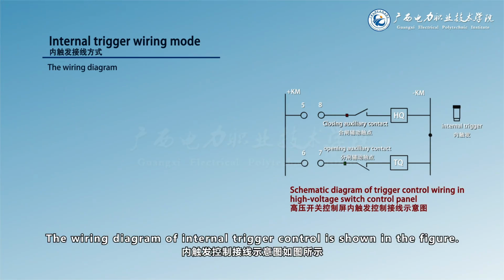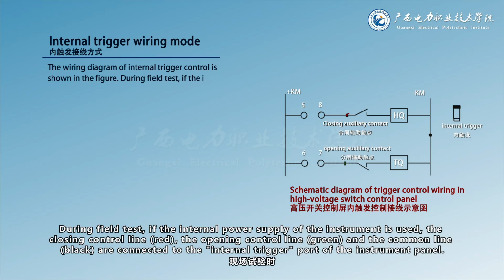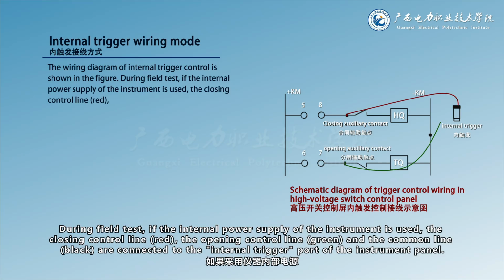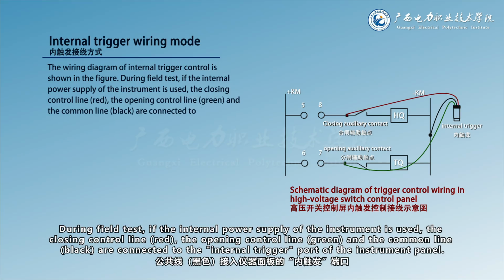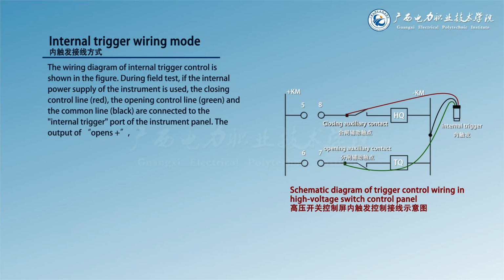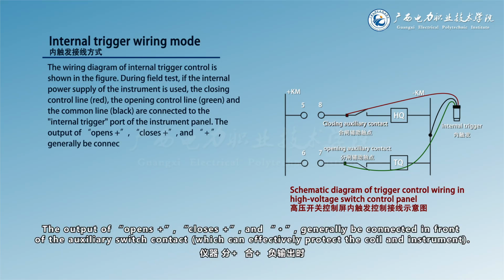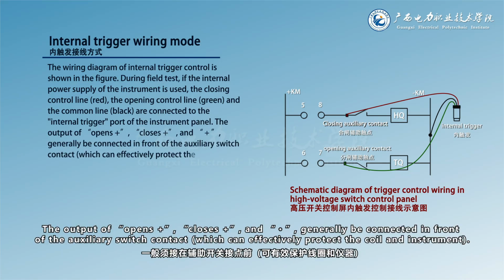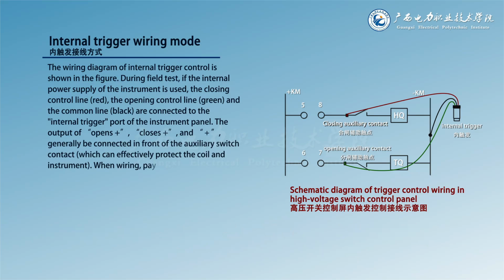Internal trigger wiring mode. The wiring diagram of internal trigger control is shown in the figure. During field test, if the internal power supply of the instrument is used, the closing control line, the opening control line and the common line are connected to the internal trigger port of the instrument panel. The output of opening and closing is generally connected in front of the auxiliary switch contact.